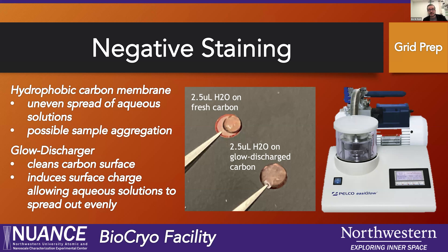We have three of these glow dischargers in Nuance — one in Tech, one in Hogan, and one here in Silverman. This is our Pelco easiGlow glow discharger. If you don't glow discharge your grids, the carbon membranes are very hydrophobic. When you drop cast your sample onto them, they bead up, don't spread out evenly, and you can end up with aggregations of your sample and completely empty areas of your grid. This process only takes about two minutes. It's not on NuCore — it's free to use — and it can really make a difference in your data.